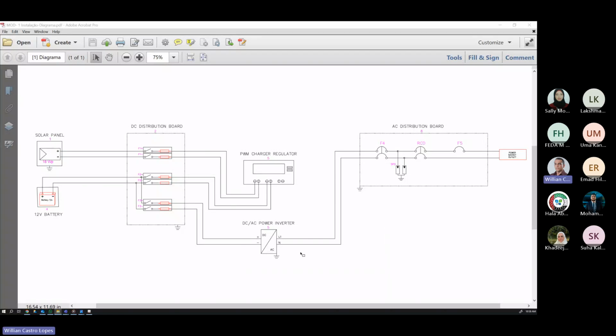On the right side we have the AC connection: line, neutral, and ground. We have F4, a bipolar circuit breaker to protect the entire circuit. We have the surge protective device that protects against high voltage in the system. We have the RCD that protects against electrical shock. And F5 will feed and protect the socket outlet specifically.